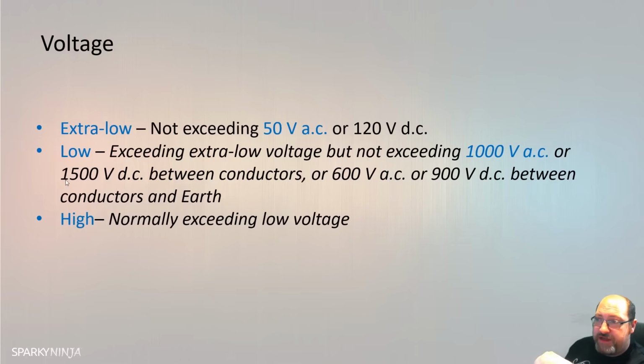High volts is over 1000 volts AC, low volts is up to that. But we have this other one, extra low. Extra low is a voltage from 0 volts up to 50 volts AC, 120 volts DC. So you'll notice, especially as we get into part 7 with regards to bathrooms and swimming pools and things like that, there'll be a lot of use of extra low voltage as a protective means. And quite often, whilst it says 50 volts there, it may be brought down even further, to 12 volts, 24 volts. So extra low voltage is a safety voltage. It's not a very practical voltage, but it's a safety voltage.